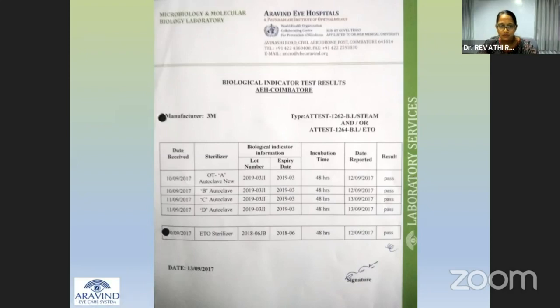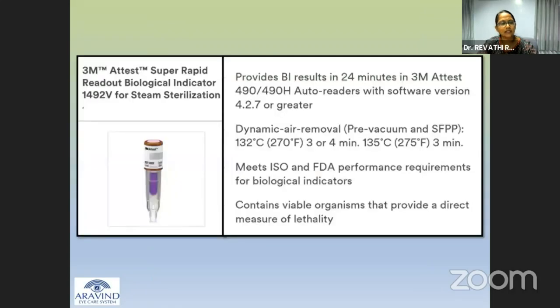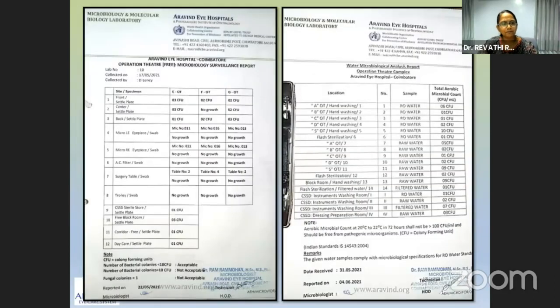Ideally, every load has to have a biological indicator, but it is not possible because of the cost and the results. At least once a week, definitely for the autoclave, a biological indicator should be passed in. Now, recently we have super fast rapid readouts, where instead of 24 hours, in 24 minutes we're able to get the results. Because of the cost, we won't be able to use it for every case.